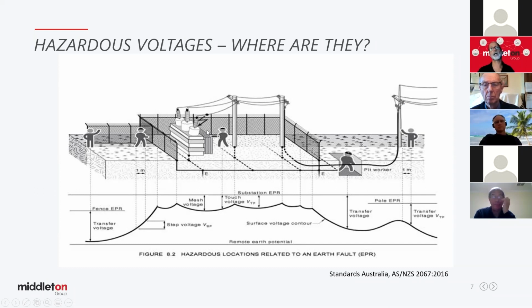So if you get this fault that they've shown on the transformer here, you'll have an EPR that's shown in this graph at the bottom. That EPR will be transferred out along the cable sheaths to a conductive pole where our friend here that's having a rest may experience electric shock. And even our friend over here near the fence on the other side, similarly, this voltage is transferred out along this conductive fence, and he may experience this transfer voltage that's depicted down here in the graph. He's actually going to experience a higher voltage than these workers that are closer to the substation, as you'll notice from that graph.